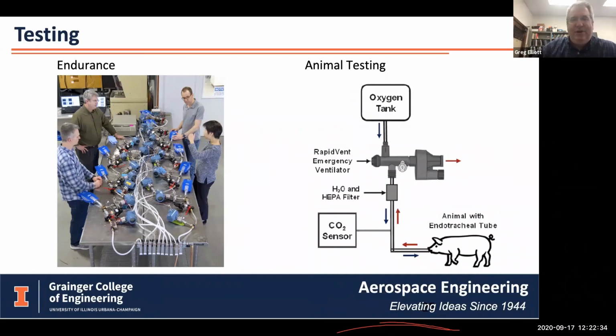In our first test, we started to have problems with acidosis in the pig, and the vets were quite concerned with that. They allowed us to do one last test, which was really good. What we had found is that we had too long of a tube, so whenever the pig wasn't able to totally get rid of the CO2 in its breathing, that was the problem. We shortened that tube, and the device was just flawless. It worked really well and was able to operate over 24 hours without a problem. The doctor was there and could even tell us what rate she wanted, and we were able to meet that with the device.